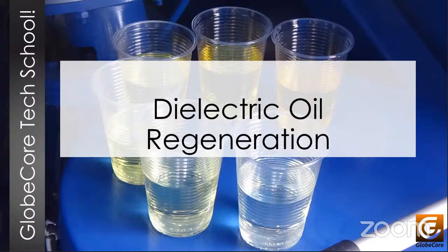So, dielectric oil regeneration. It's not a new process by any stretch. It's been around for quite a few years. This process has been in development over the years, and there are also standards developed for this process that include quality criteria. We're going to mention the IEC 60422 standard. And there is the mineral oil regeneration guide and criteria for use, and that is the IEEE C57.637. That latter standard was introduced in 2015. So these standards will give us the necessary definitions and all of the parameters, and we can learn a little more about those processes now.